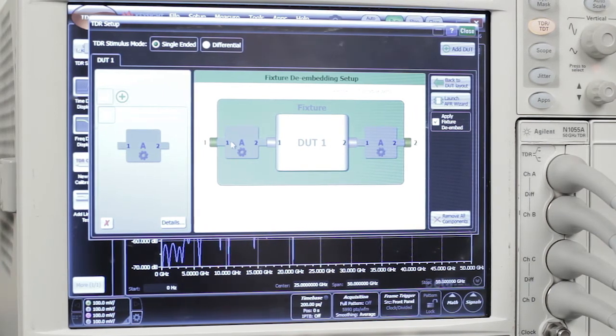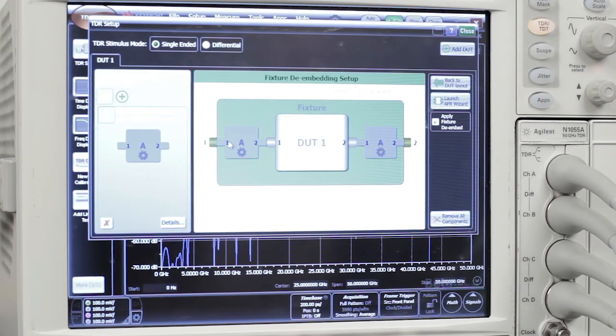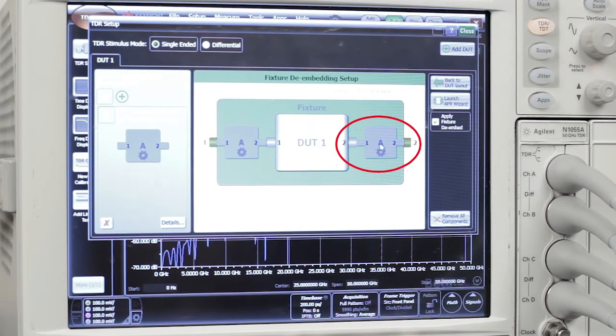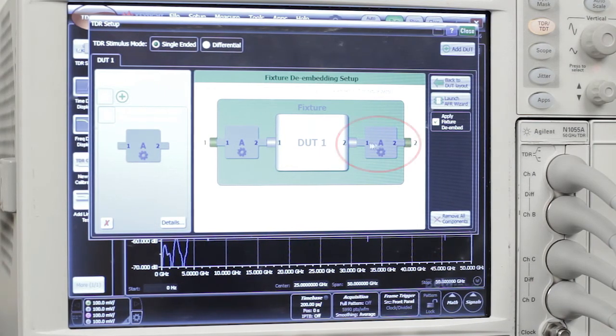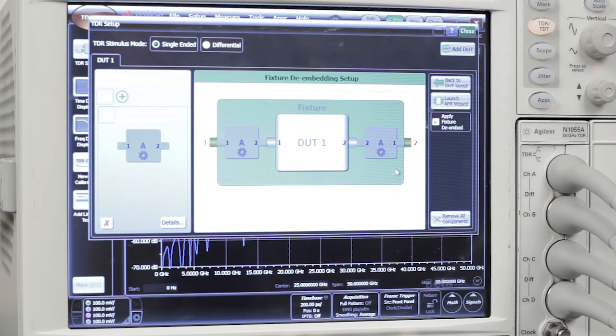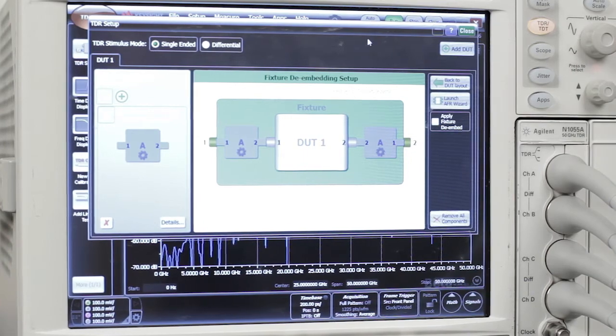Port one of the fixture is the connectorized port, which is connected to the TDR. So over on this port, we need to change the configuration of the fixture. So port one is connected to the TDR and port two is connected to the DUT. And it's very easy to reverse those. So there you go. By checking this box, we can remove the fixtures. By unchecking it, we'll have the fixtures in place. Let's leave it unchecked for now.